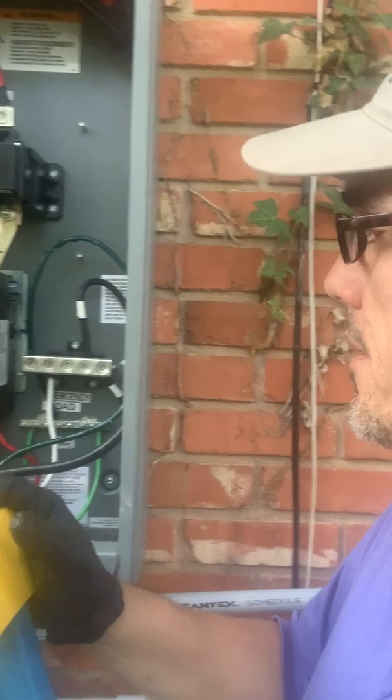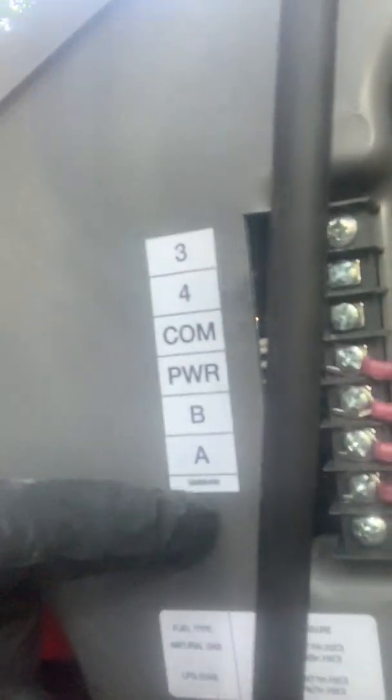I tested to confirm that the bonding at my sub panel and at the ATS is correct. I used wires that exceed carrying capacity as required. The only issue the Kohler technician found was that I had the control wire connections shifted — my A terminal was in the wrong position. He fixed that, ran a test, and everything checked out.